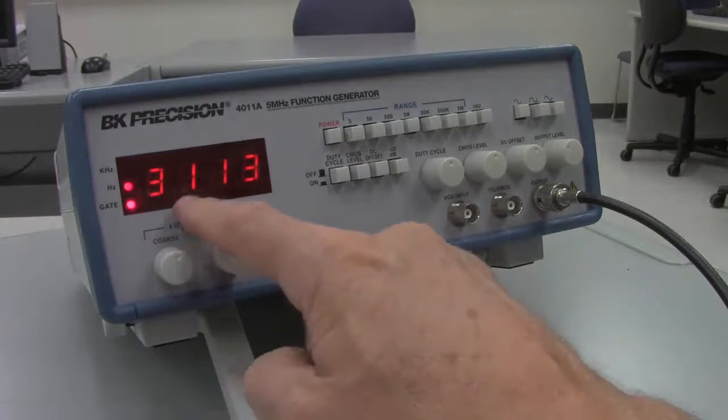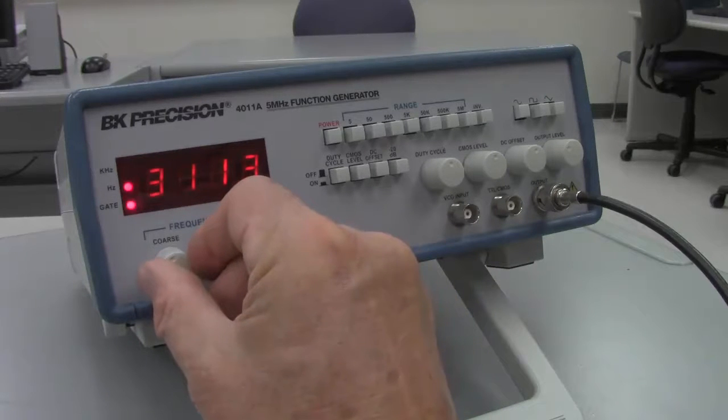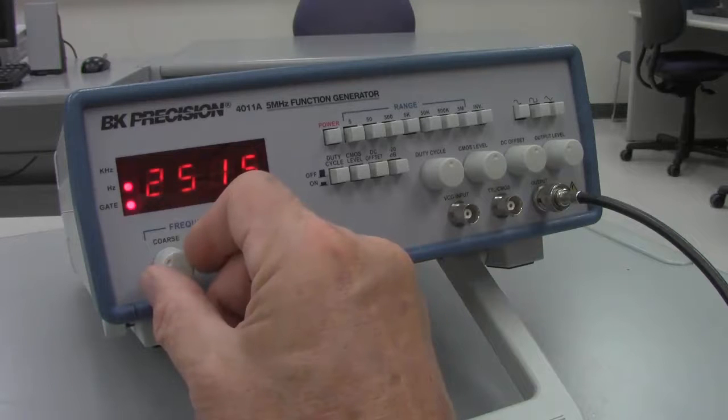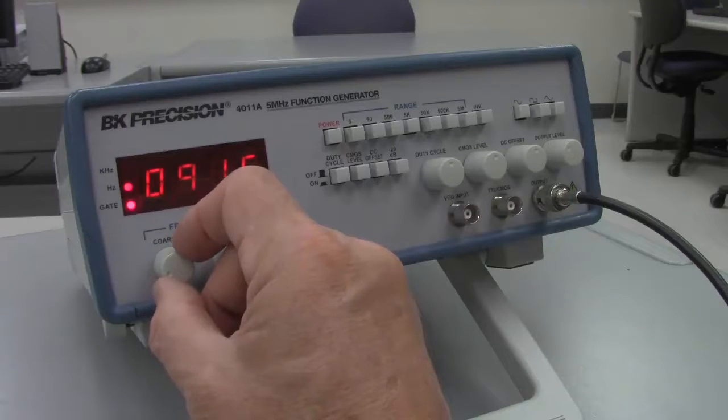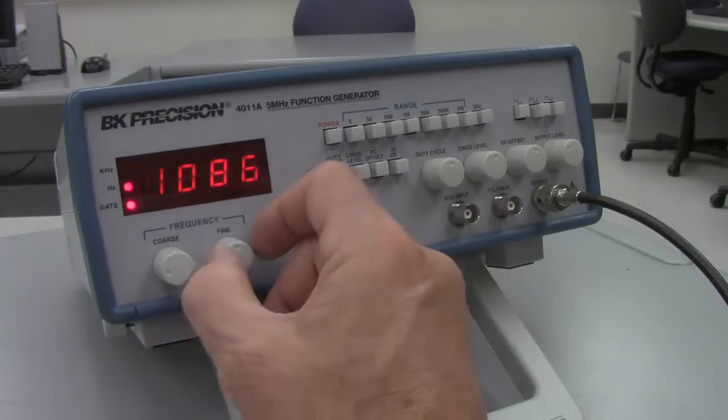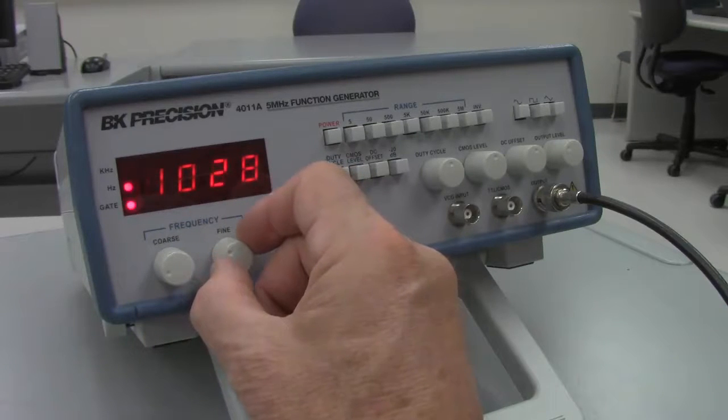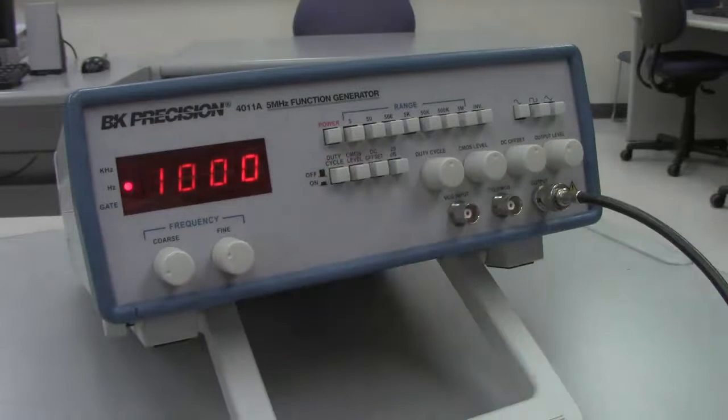It comes up and tells me that it's about 3,113 hertz, or 3.1 kilohertz. So let's just go ahead and adjust it down. I'd like to get pretty close to 1,000 hertz. Using the coarse adjustment to get close, now let's just try to adjust it down using the fine adjustment, and we get down to 1,000 hertz.